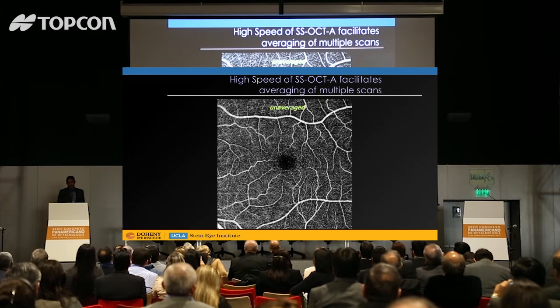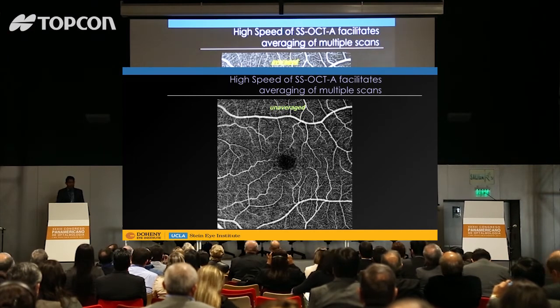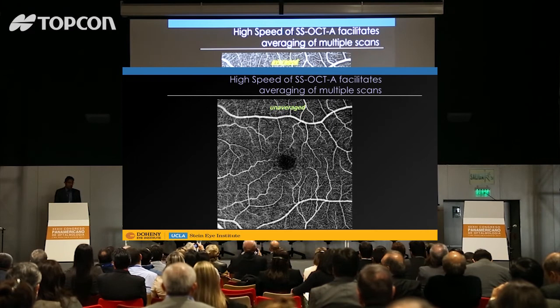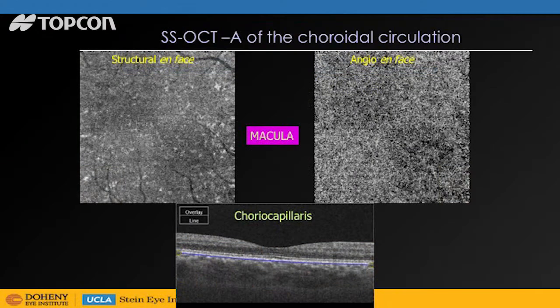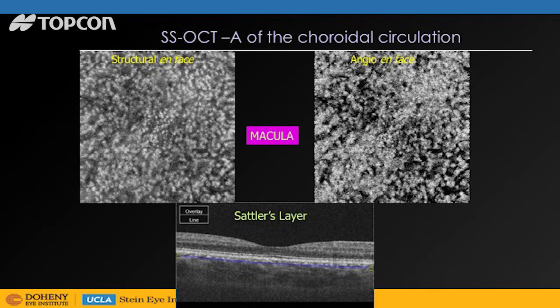One of the biggest advantages is that if you have high-speed swept source OCT, you can more easily average multiple scans. Averaging scans can substantially improve the quality of OCT imaging and have substantial impact on quantitative measurements from OCT angiography — we've published on this recently in ophthalmology. Additionally, swept source OCT can do a nice job of evaluating the choroidal circulation. You can get very nice imaging of the choriocapillaris in normal patients with spectral domain OCT, but you do see some signal even in some of the medium vessels with swept source OCT. Even with swept source, for very large vessels in the absence of RPE atrophy, it's still difficult to see flow because there is still some signal loss.